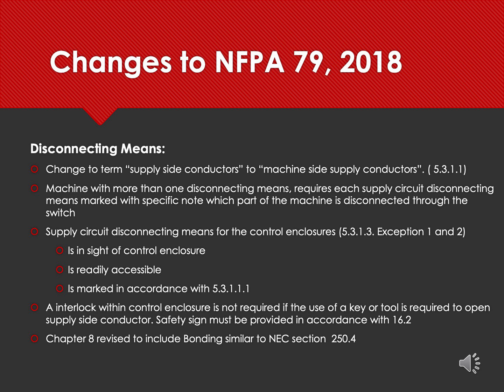which brings the clarity. It is not a supply conductors on anything. It's basically referring specifically to call it out as a machine side supply conductors. And then throughout the text, the term incoming supply circuit is replaced with machine supply circuit, again to be consistent and be specific in the terminology. And the next point is the disconnect means can be integral to the machine, or it can be separate within the line of sight, and also it's readily accessible and is marked in accordance with 5.3.1.1.1.